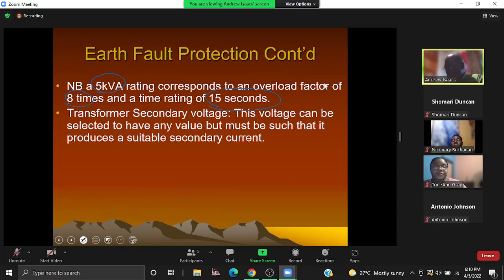So we have looked at, we have used the equivalent resistance in terms of finding the current that will flow through the earthing point. We have used that current and the maximum knee point voltage of your transformer to determine the rating of the transformer. But I also gave you at the beginning that the secondary voltage must be between 100 and 500 volts. So I know what the primary voltage is. I know what the rating is. I now need to find a suitable secondary voltage. All right?